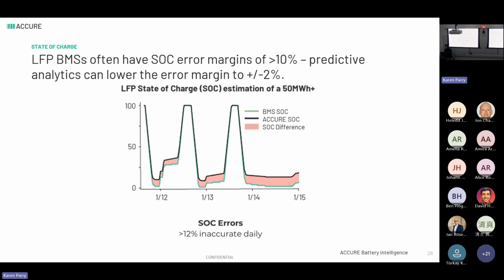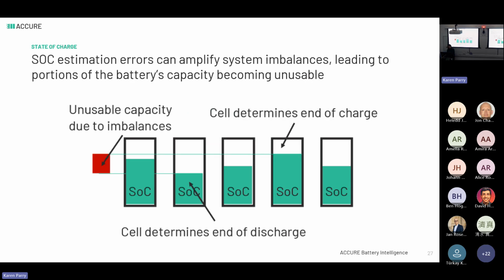Part of why this is important is it's not just looking at one battery. If batteries are in series, the highest charge battery determines when charging stops, and the lowest level of charge determines when discharging stops. So any difference in these charges is unusable capacity.